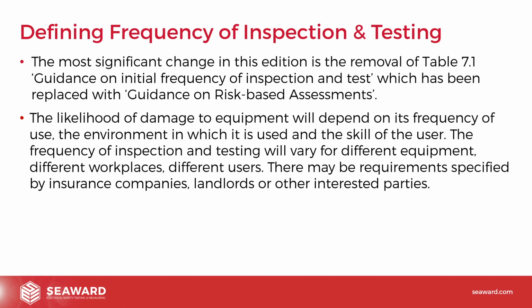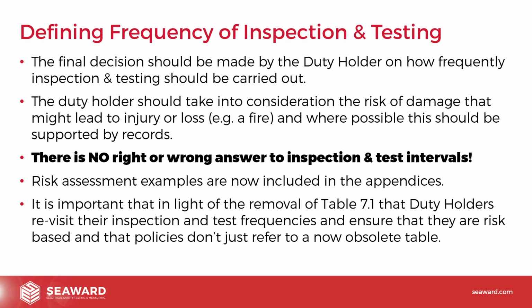So these are all important points, and we'll go into a bit more detail in the coming slides. So the final decision should always be made by the duty holder on how frequently inspection and testing should be carried out. The duty holder should take into consideration the risk of damage that might lead to injury or loss, and where possible this should be supported by records. Now, an important point, we've put it in bold to emphasise it: there's no right or wrong answer to inspection and test intervals, inspection and test frequencies. The right answer is the answer that's been arrived at by doing a risk assessment and assessing the risk and using inspection and testing as a control measure to control the level of risk that the duty holder perceives.